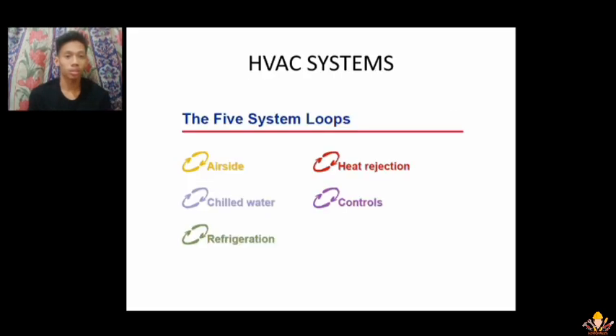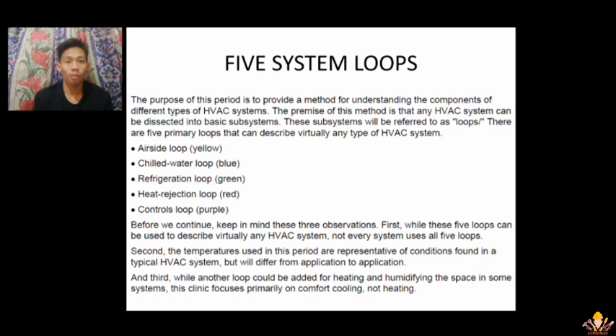We have the HVAC systems, and the 5 system loops are airside, chilled water, refrigeration, heat rejection, and controls. The purpose of this period is to provide a method for understanding the components of different types of HVAC systems. The premise of this method is that any HVAC system can be dissected into basic subsystems. These subsystems will be referred to as loops. There are 5 primary loops that can describe virtually any type of HVAC system. We have the airside loop, the chilled water loop, the refrigeration loop, the heat rejection loop, and the controls loop.